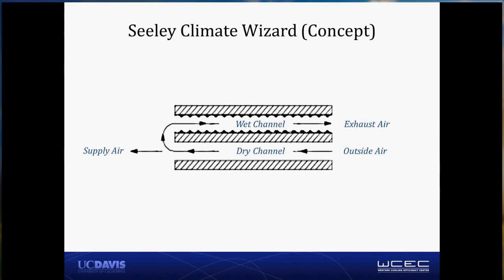The Seeley system also recirculates some of the air from the dry channel to the wet channel inside the heat exchanger, though you should differentiate their approach from Coolerado's, especially by the fact that they allow all of the primary air to pass through that dry channel before taking a portion of that air and recirculating it to the inlet of the wet channel where the evaporative process occurs. Of course, evaporation occurs in that channel and drives the cooling effect for the dry channel. So you'll see the results, but they are also able to drive below the wet bulb condition of the inlet air under certain scenarios.